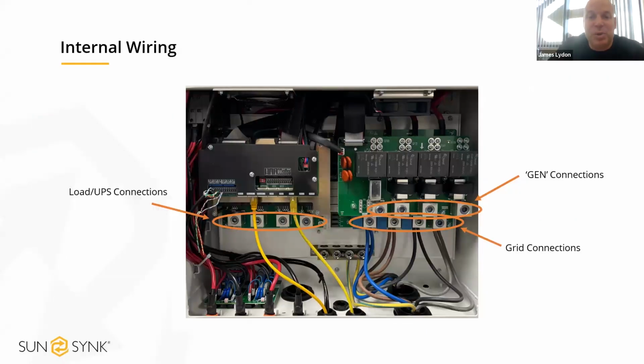Internal wiring. So this is just showing you a little overview of the inside of the 50 kilowatt hybrid inverter. So there's plenty of wiring space in there. And you can see there's three different lots of connections. We've got our load and UPS connections. So if someone doesn't have that UPS load wired in, these are going to be redundant. But if you do have that critical load connected, they will be connected to these ports. Top right, you've got your generator connections. So that's what your backup generator would be connected to. And then you've got your grid connections just underneath.